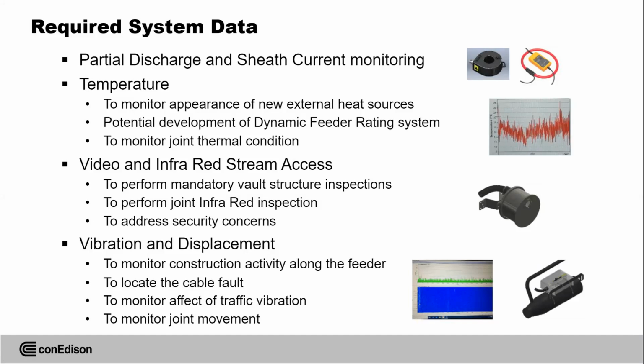Also, we are planning to use a DTS system to monitor joint thermal condition. We all know the joint should be a kind of heat sink, the coolest part of the cable because of its size. But in reality, it's not exactly true, because in the summertime, since we install them in underground vaults, the temperature in the joints can be higher than the ambient temperature of the soil surrounding the feeder.